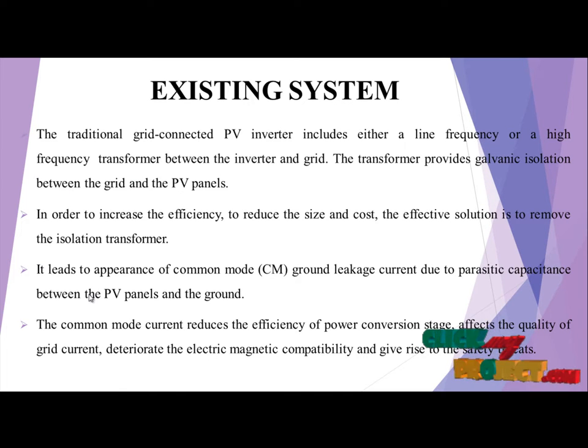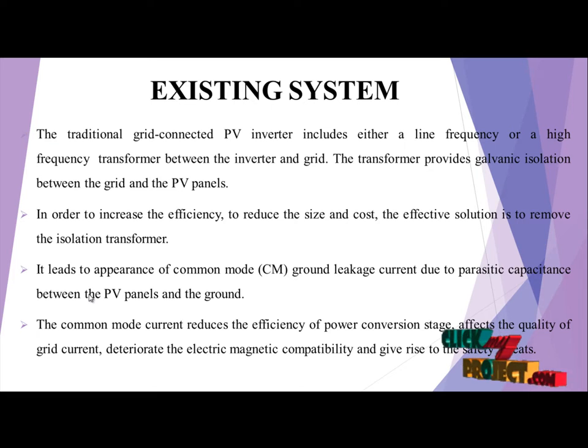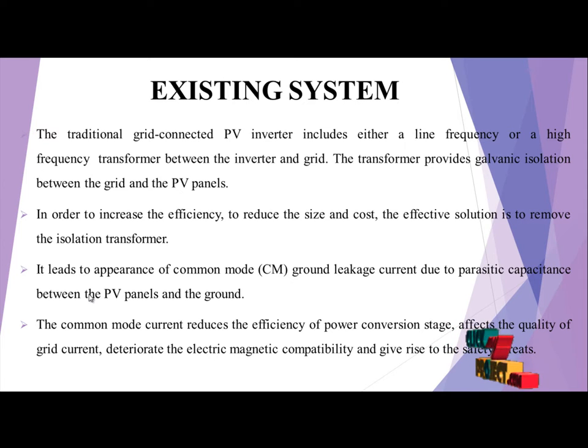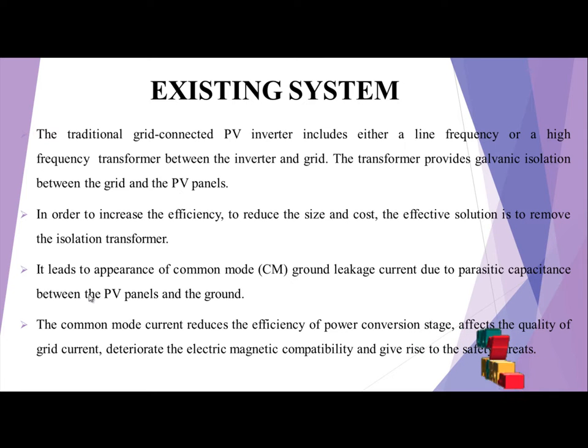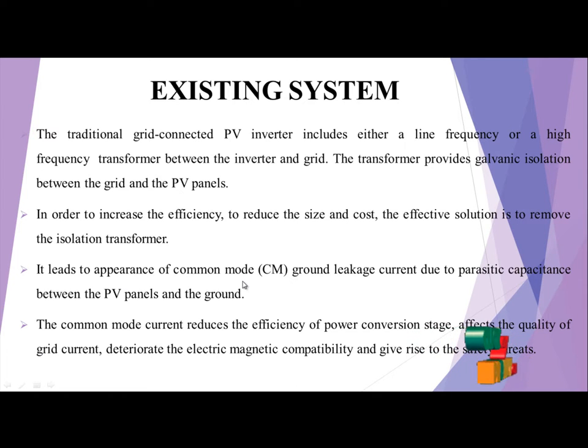In the existing system, the traditional grid-connected PV inverter includes either a line frequency or high frequency transformer between the inverter and grid. The transformer provides galvanic isolation between the grid and PV panels. In order to increase the efficiency, reduce the size and cost, removing the isolation transformer is proposed, but it leads to the appearance of common mode ground leakage due to parasitic capacitance between the PV panel and ground. The common mode current reduces the efficiency of power conversion, affects the quality of grid connection, deteriorates electromagnetic compatibility, and gives rise to safety threats.